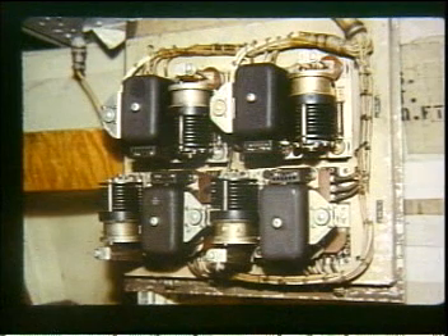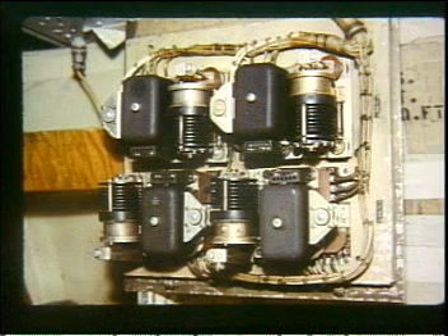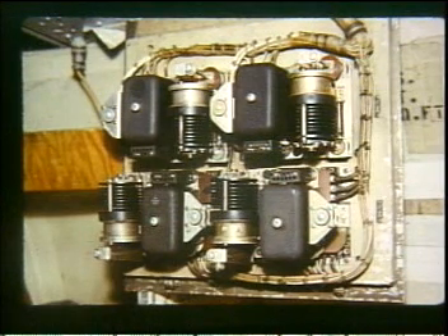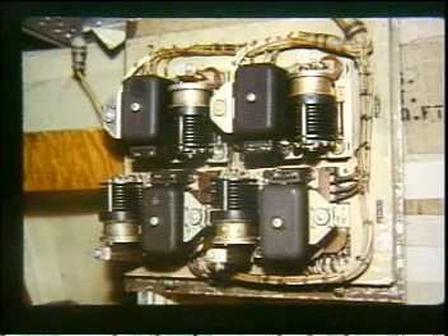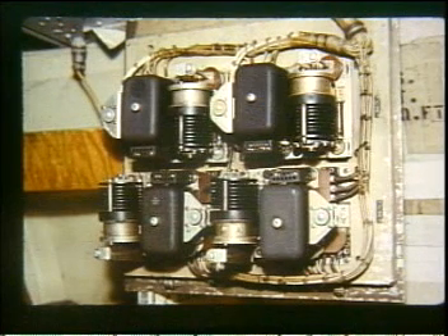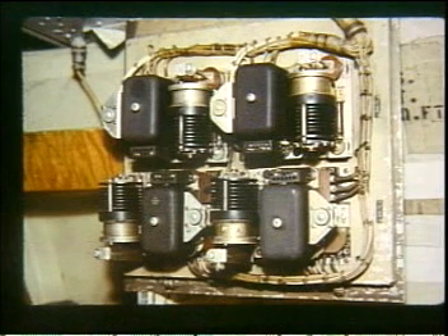A generator control panel for each generator is located in the voltage regulator compartment of the main junction box. The generator control panel will maintain generator output voltage at 27.5 volts. It connects the generator to the master bus when the generator voltage exceeds the bus voltage by a slight amount. It will parallel or equalize the voltage output when more than one generator is connected to the bus, and will disconnect the generator from the bus whenever output falls below bus voltage.